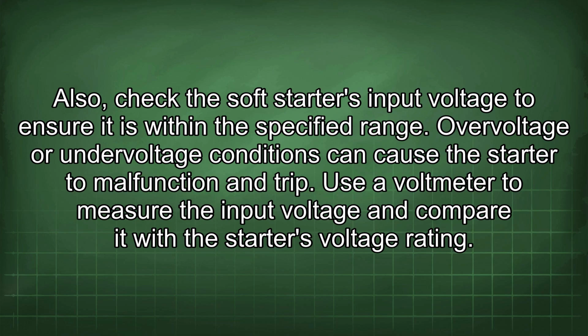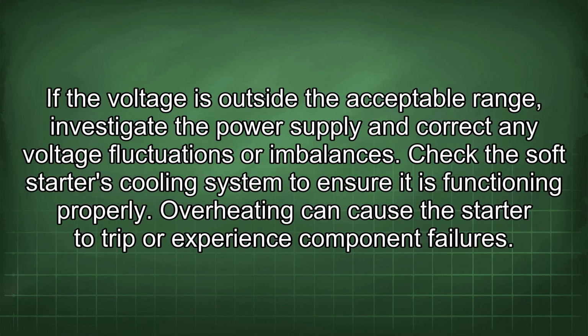Overvoltage or undervoltage conditions can cause the starter to malfunction and trip. Use a voltmeter to measure the input voltage and compare it with the starter's voltage rating. If the voltage is outside the acceptable range, investigate the power supply and correct any voltage fluctuations or imbalances. Check the soft starter's cooling system to ensure it is functioning properly. Overheating can cause the starter to trip or experience component failures.